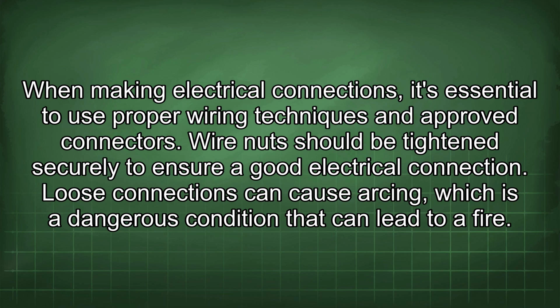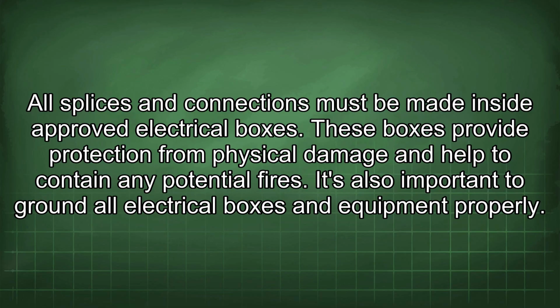When making electrical connections, it's essential to use proper wiring techniques and approved connectors. Wire nuts should be tightened securely to ensure a good electrical connection. Loose connections can cause arcing, which is a dangerous condition that can lead to a fire. All splices and connections must be made inside approved electrical boxes. These boxes provide protection from physical damage and help to contain any potential fires.